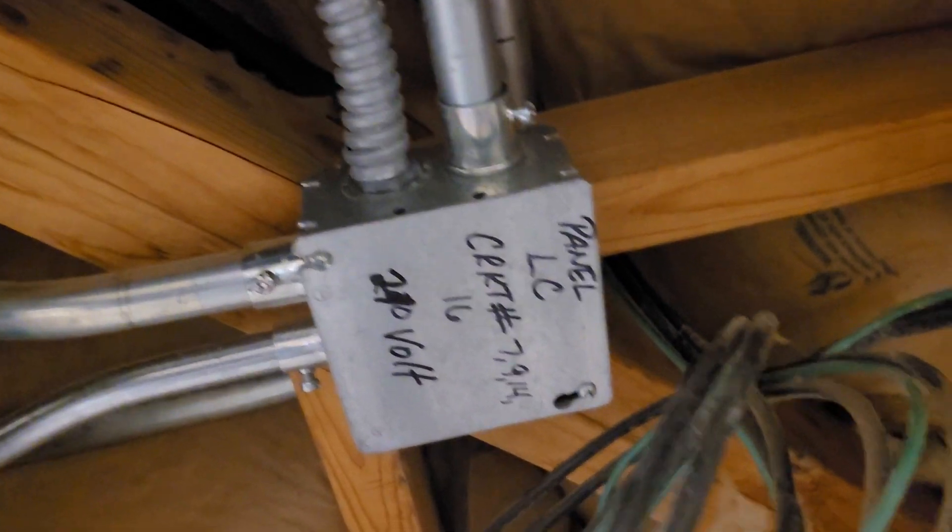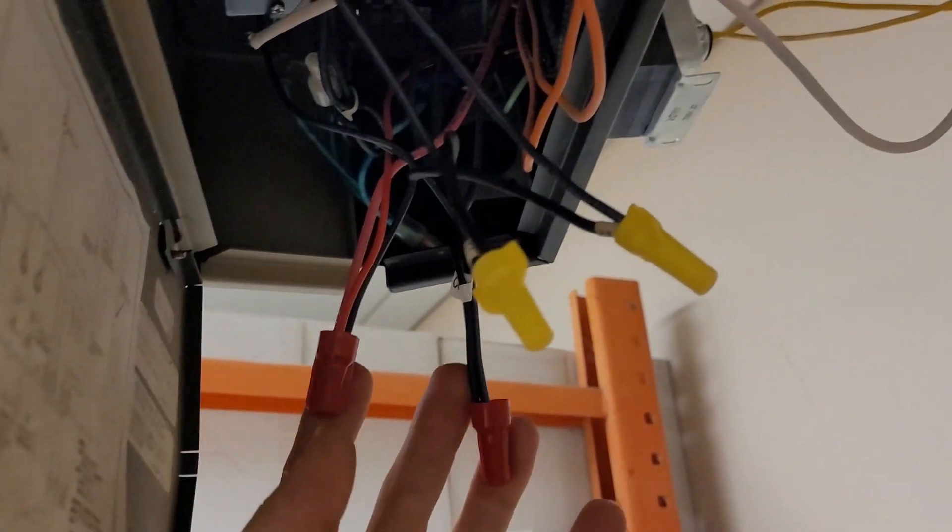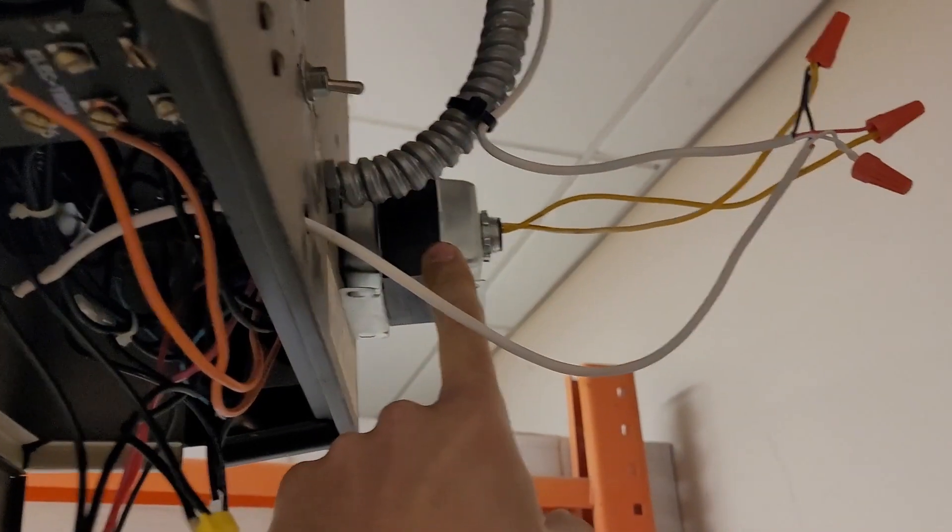I'm gonna turn it off so I could work on it. 208 volts, so I got a 208 volt transformer and I wired it in to leg one and leg two coming from the breaker, and it's gonna step down 208 to 24 volts.